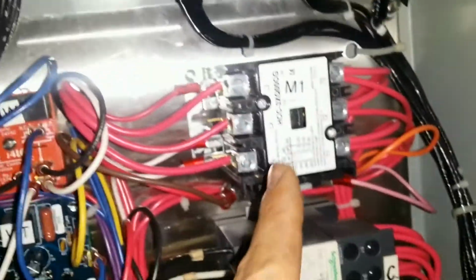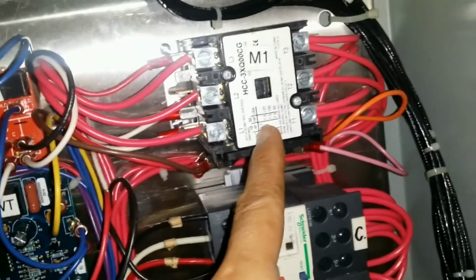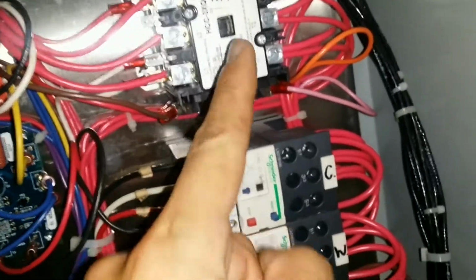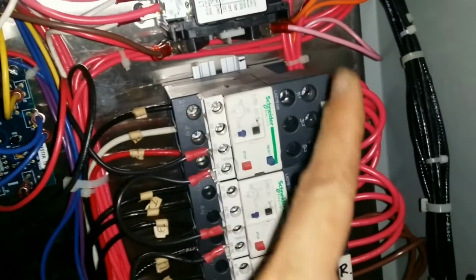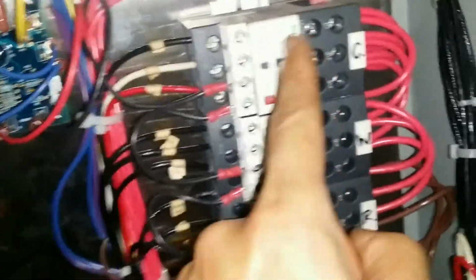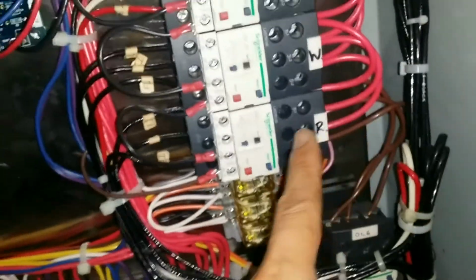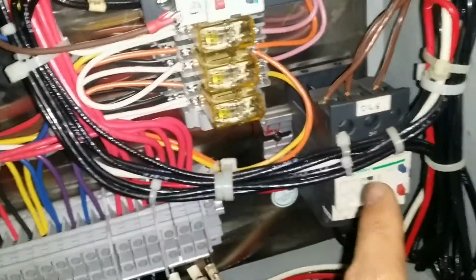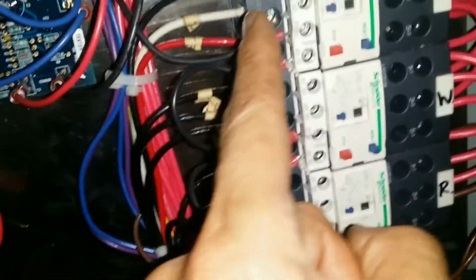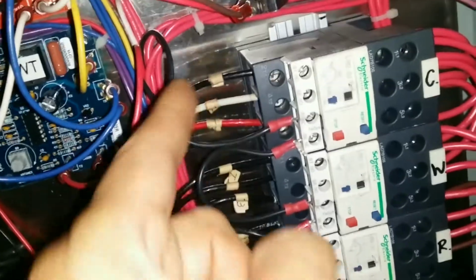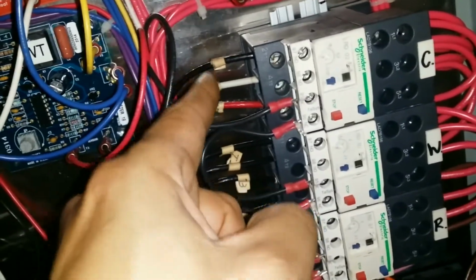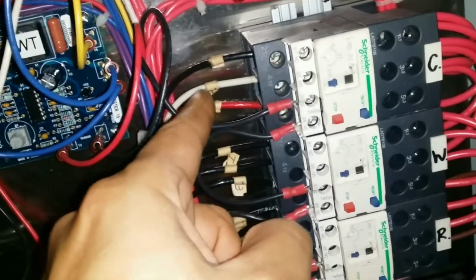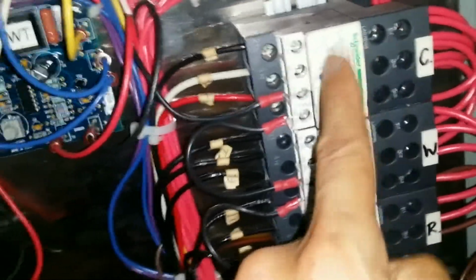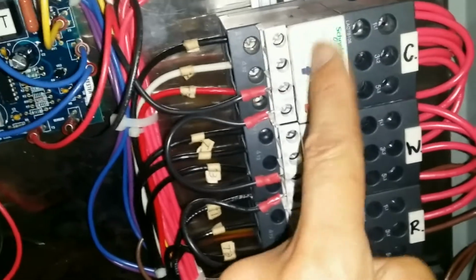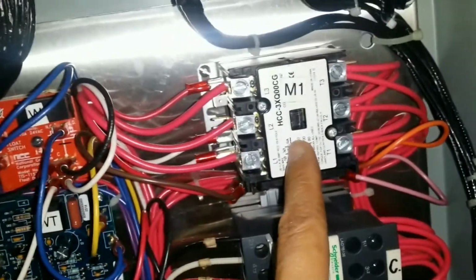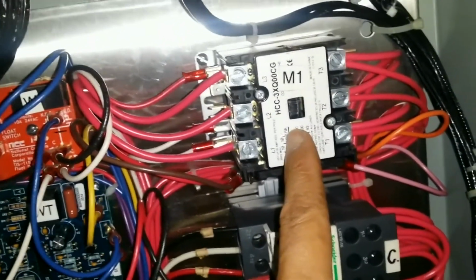So here is my main contactor, and when this contactor energizes, all of those motors get power. But all that power gets distributed and jumpered, as you see over here, to all of these overloads. And then after the overload is when it goes to each motor. So if one motor gets stuck and starts drawing too much power, this overload will open and it will cause this contactor to de-energize, stopping all motors.